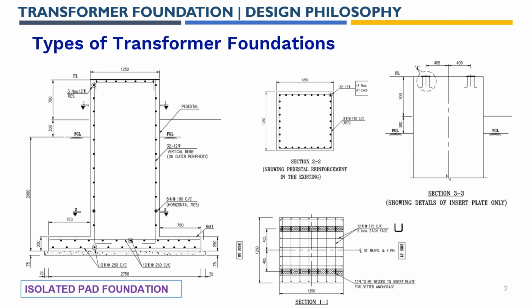There is no requirement of oil containment or bund wall around these transformers, so this can be adapted for dry type foundations. This is a sectional view of the pedestal showing the reinforcement around it, with nearly 32 numbers of 12 diameter rods placed here.